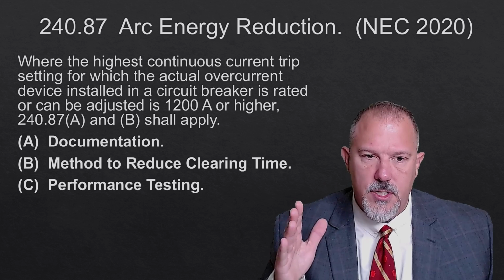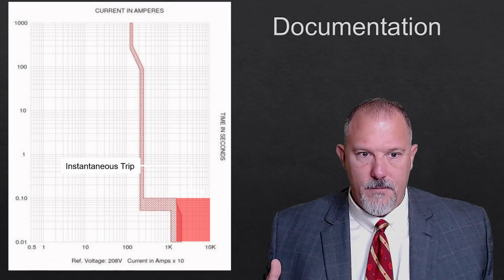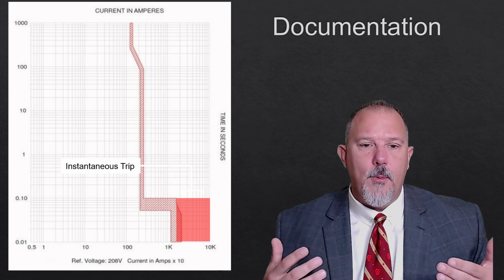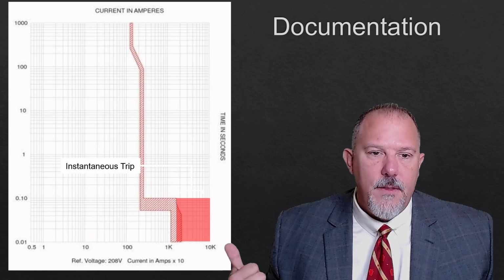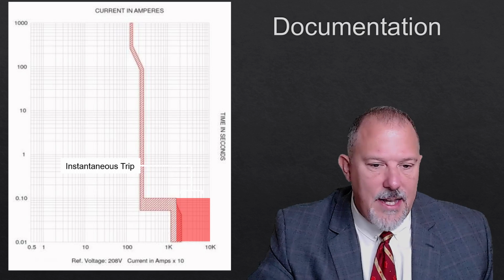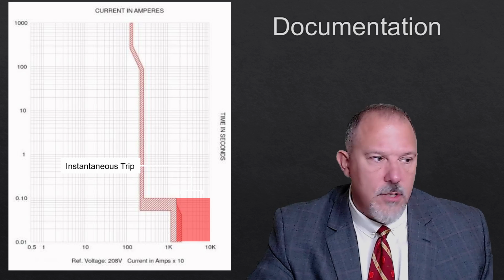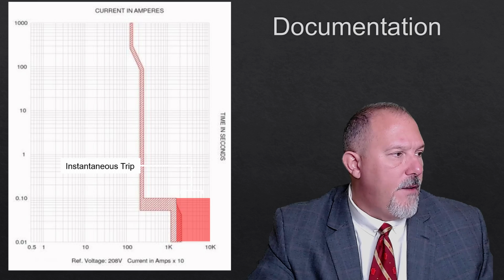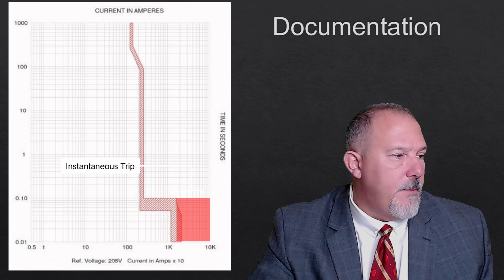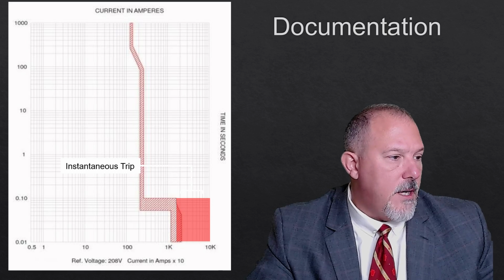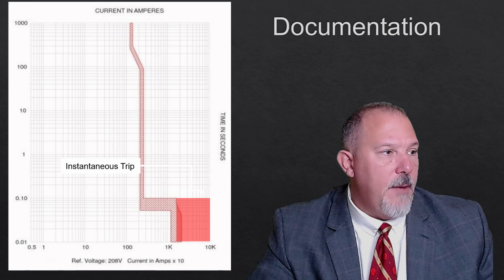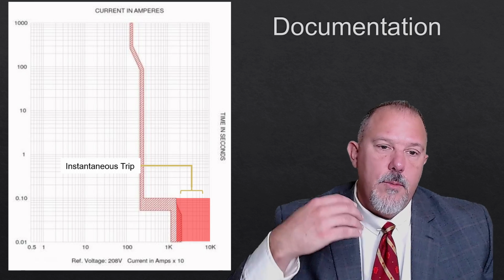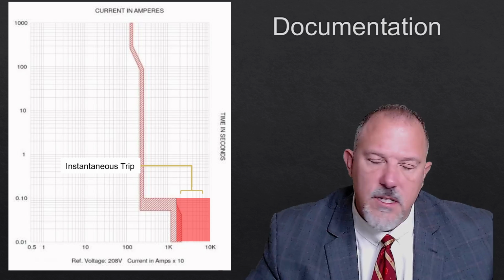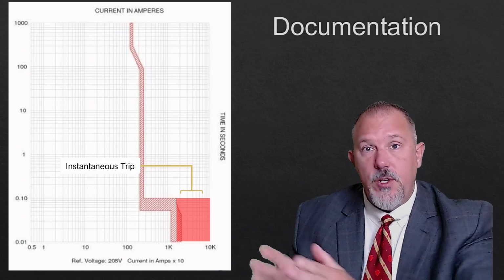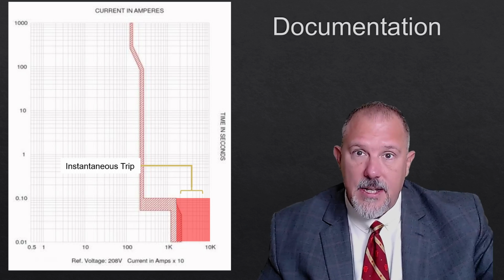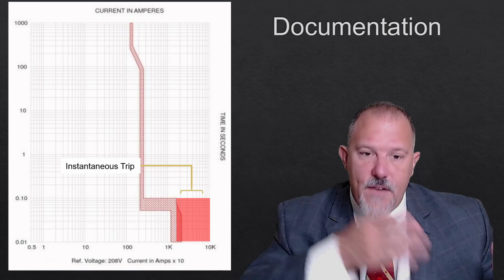So you have methods to reduce incident energy, and it's all about the clearing time. So if I have a system that can operate in this red region right here, where I clear that instantaneous trip, where I clear the fault as fast as I can, there is no intentional delay when in that area of the trip curve. That is a critical piece of the pie with regard to being able to clear the faults. I want to be able to take that fault current off as fast as possible. You saw why, right? Right in the beginning, I showed you videos: 6 cycles, half cycle, quarter cycle. The faster I can clear, what's a quarter cycle?